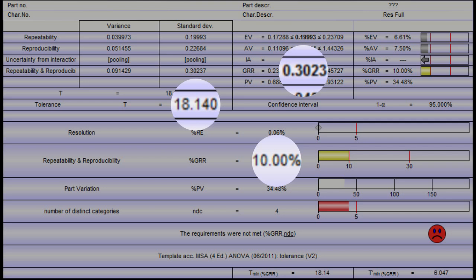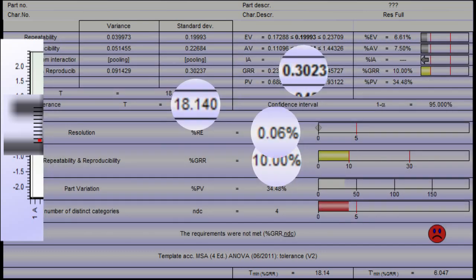In other words, if the tolerance is 18.14 or more, the gauge R&R is ok. The resolution was 0.01 which is 0.06% of the tolerance way below the criteria of 10% but the NDC is only 4. Is it a problem? Do we need to change something about the measuring devices?